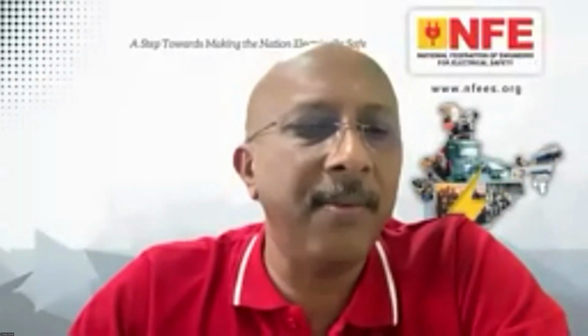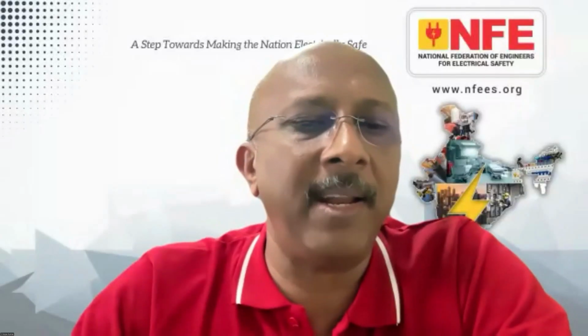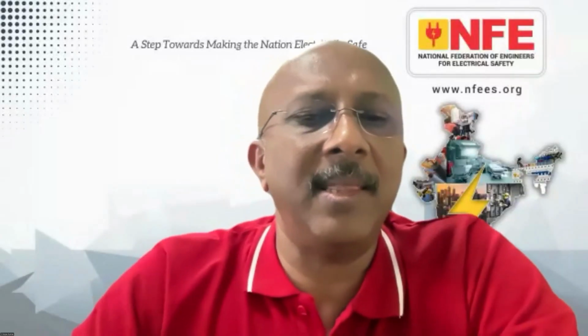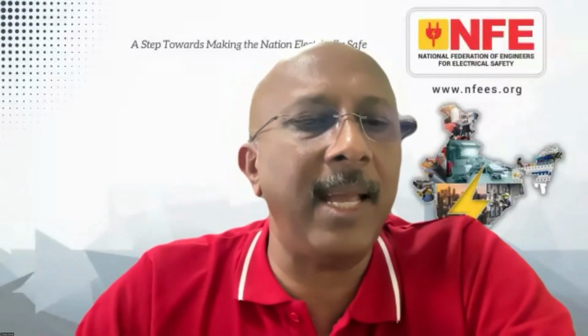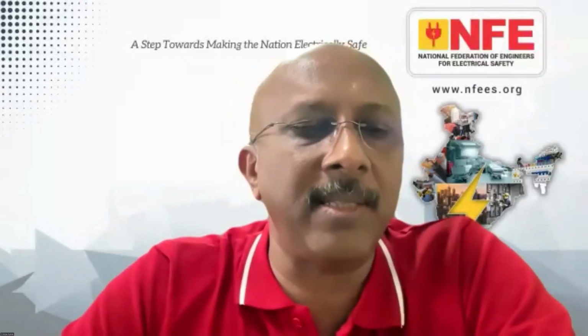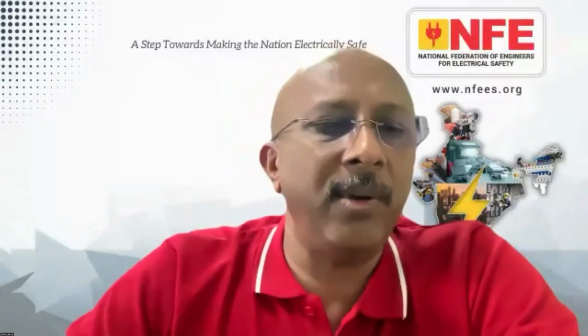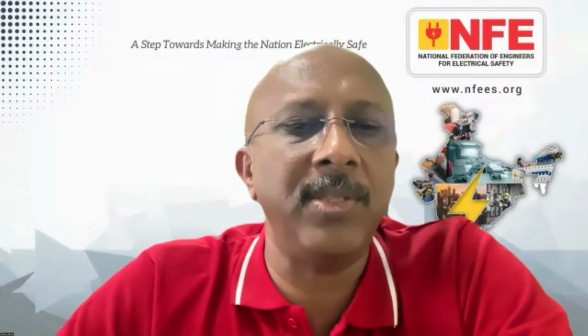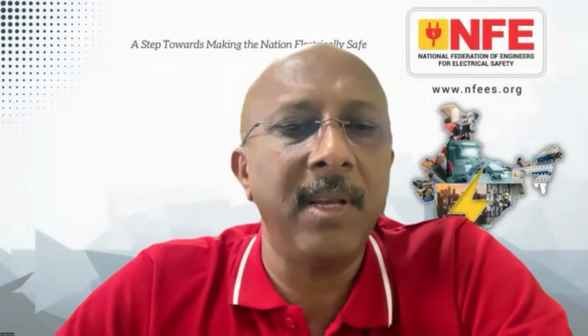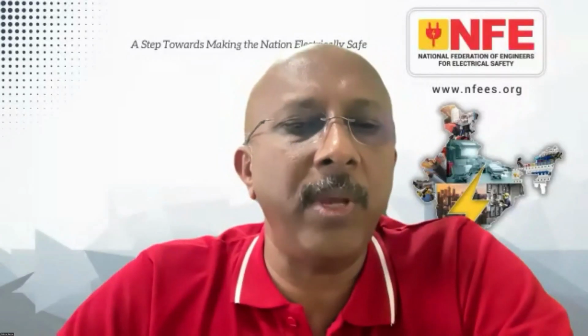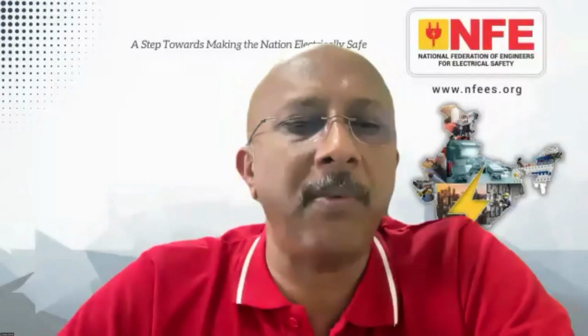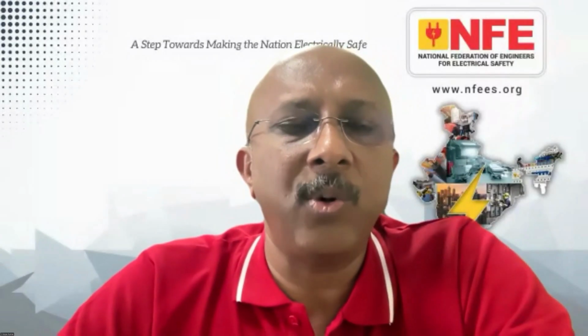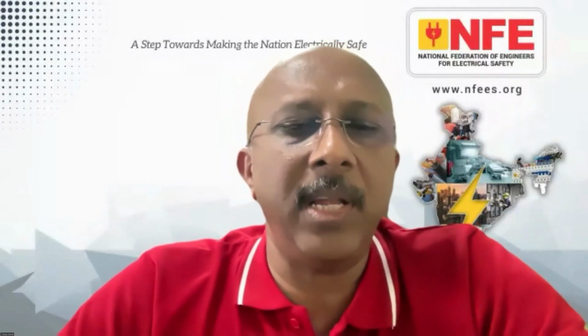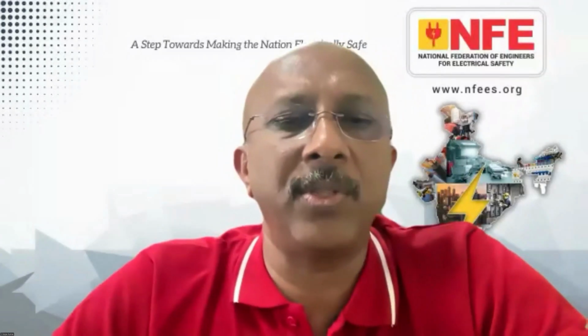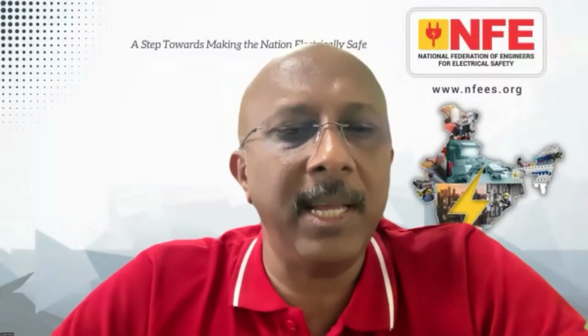If somebody gave a patent to this particular device, then we have to really look at the capability of the patent office. This is nothing new. This has been there in science since the invention of electricity. During the 1880s, the system used was the IT, unearthed system. Then they switched over to the earthed system due to the problems of double fault. So don't say that this is an innovative system or something special. This is basically an IT system.